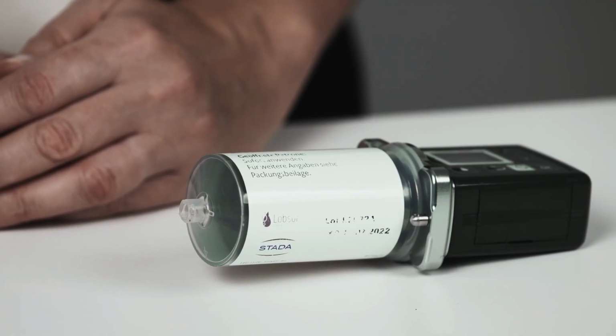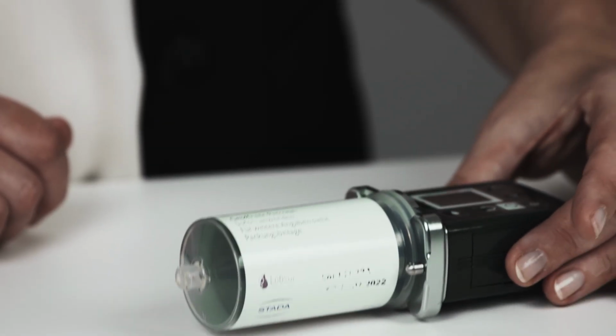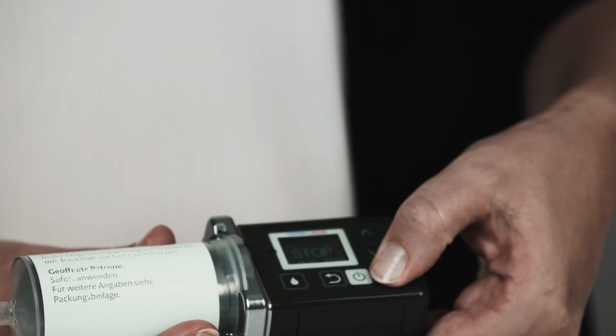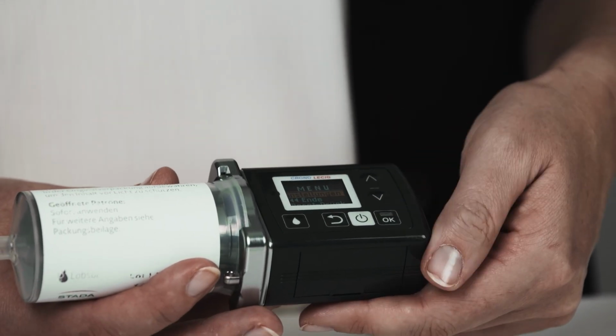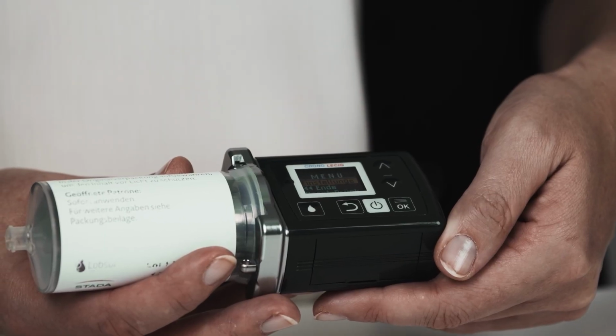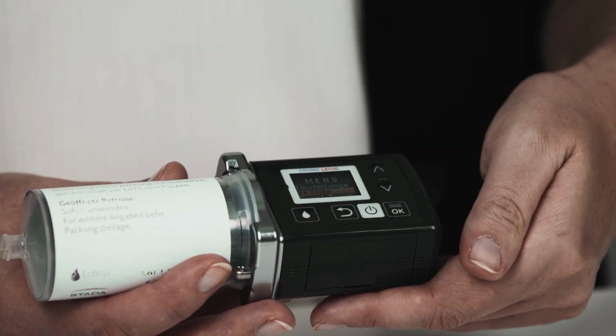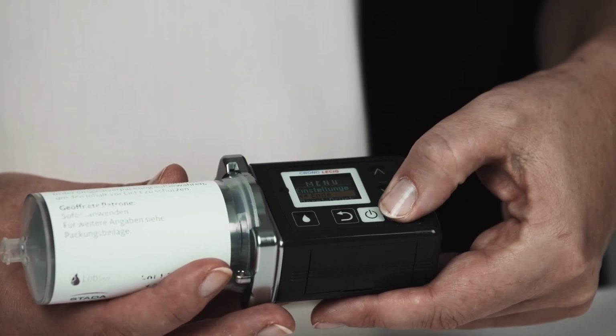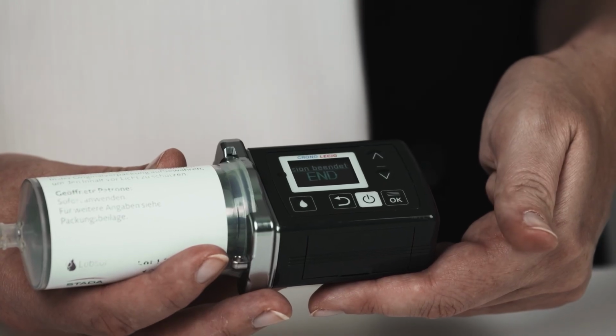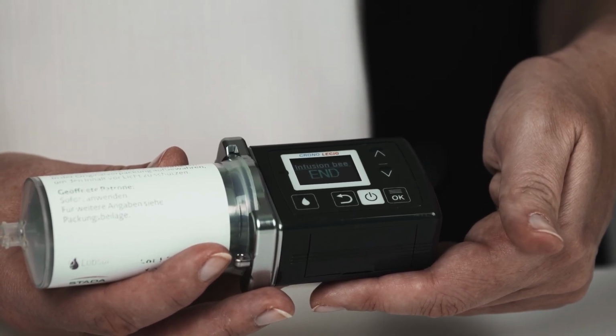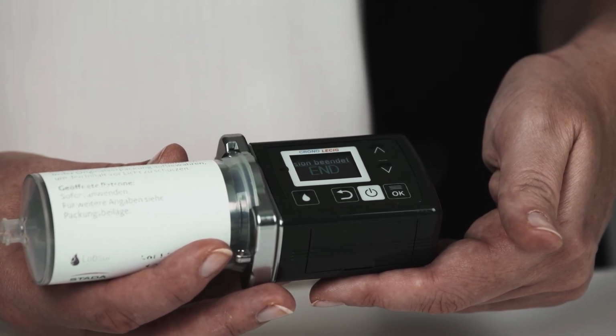Press any key to turn on the display. Press and hold the OK key. The display shows the main menu. Press the lower arrow key and select End. Press OK to confirm. After 10 seconds, the piston is retracted. This process takes approximately 6 minutes. While you are waiting for the piston to be fully retracted, complete the following steps to flush the probe.